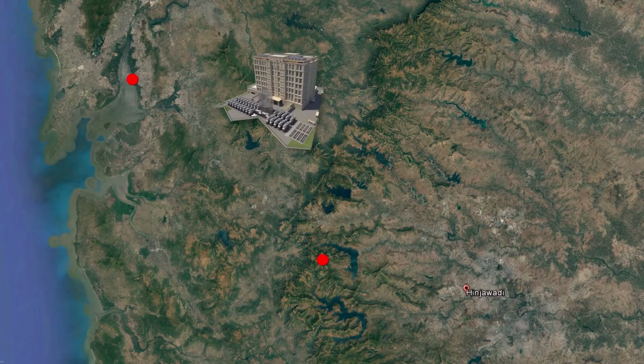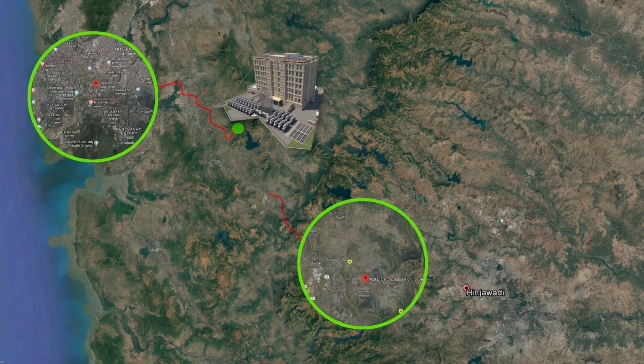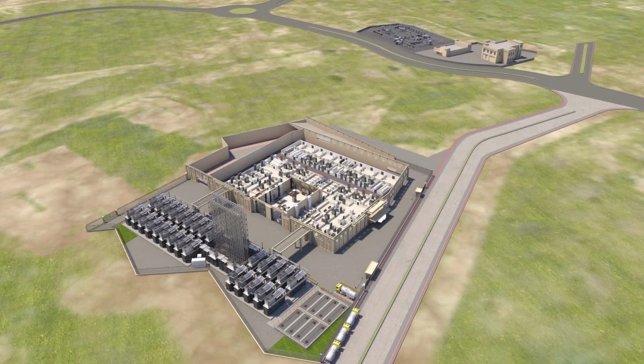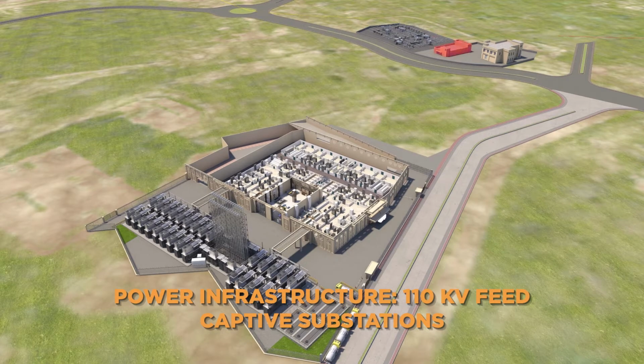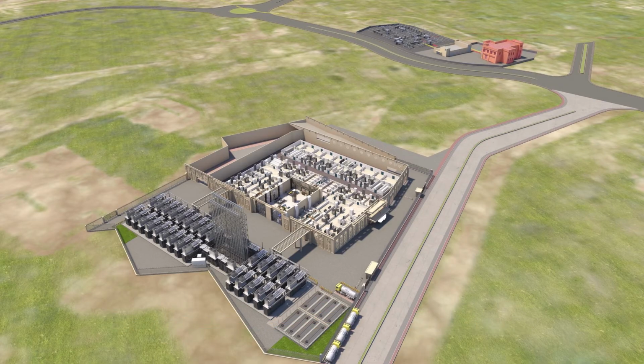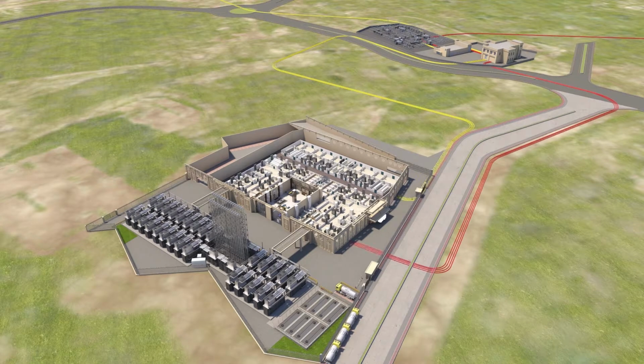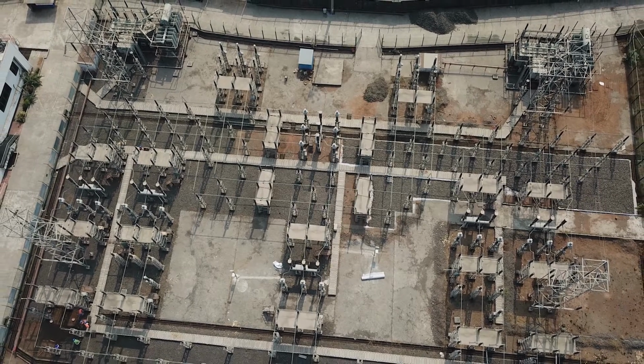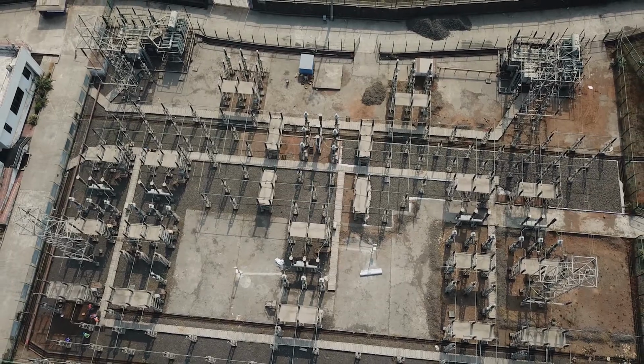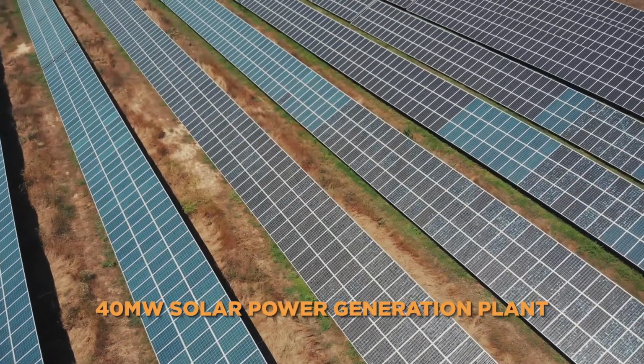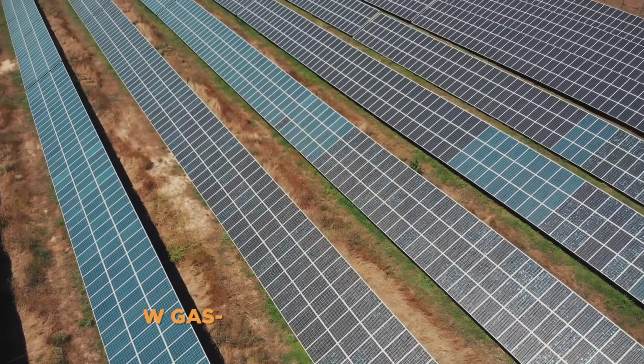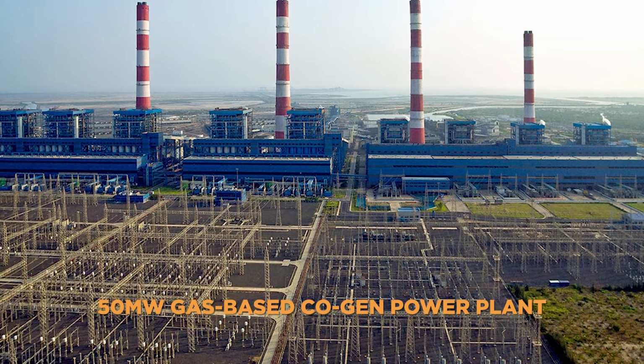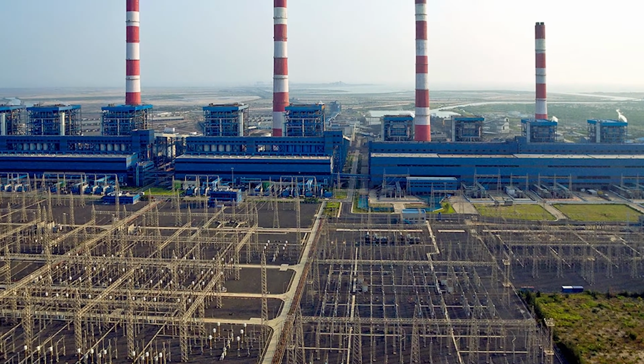Yotta NM1 receives power at 110 kilovolt from two upstream transmission substations and has a dedicated 110 by 33 substation and 33 by 11 substation right adjacent to the facility. Four numbers of 11 kilovolt lines in N plus N mode, each carrying 12.5 megawatt, supplies power to Yotta NM1. Our affiliate company manages the power distribution operations with a distribution license. Soon, Yotta NM1 will be powered by a captive 40 megawatt solar power plant and a captive 50 megawatt gas-based cogeneration power plant adjacent to our data center park.